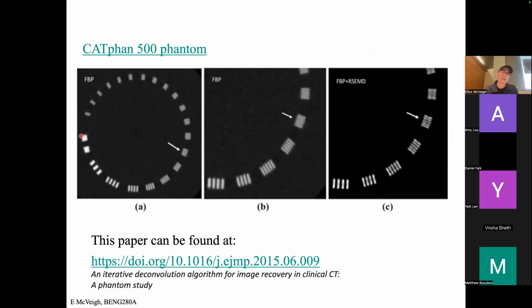This is kind of like the hole phantom that we did a problem set with, as the holes got closer and closer together, you measured the contrast changing. Same for this. As the frequency of these bars goes up and their gaps diminish, eventually you say, this is the last set of bars that I can detect before I can no longer tell you that they're bars of a certain frequency. And so that's my highest spatial frequency.